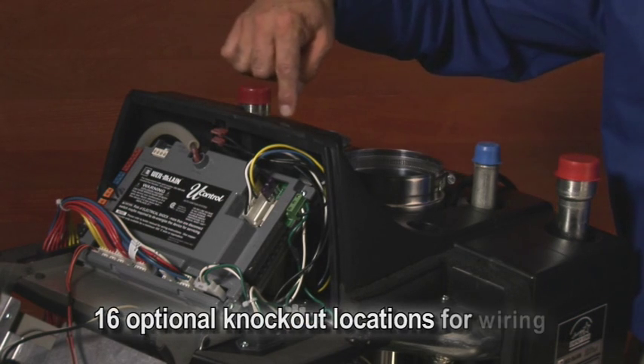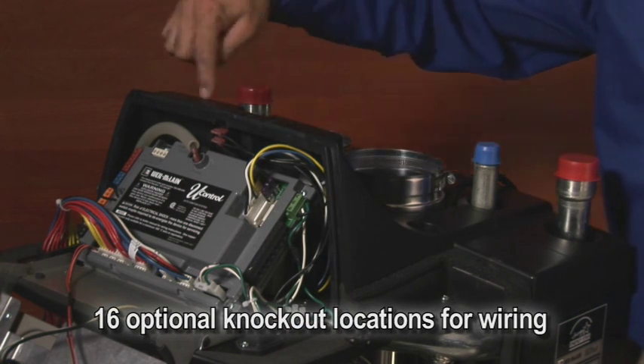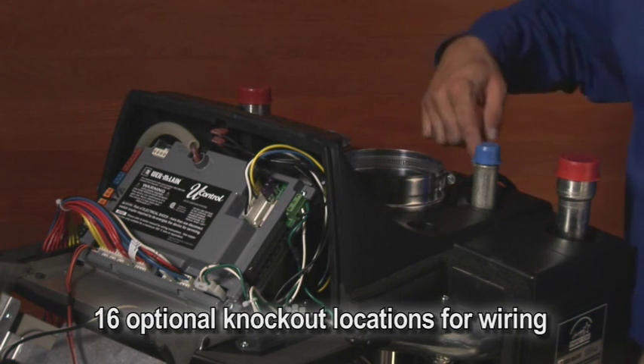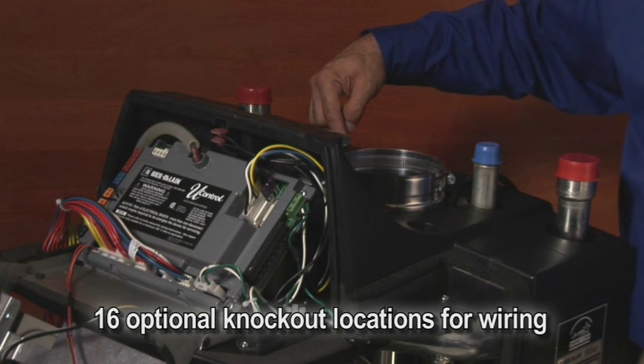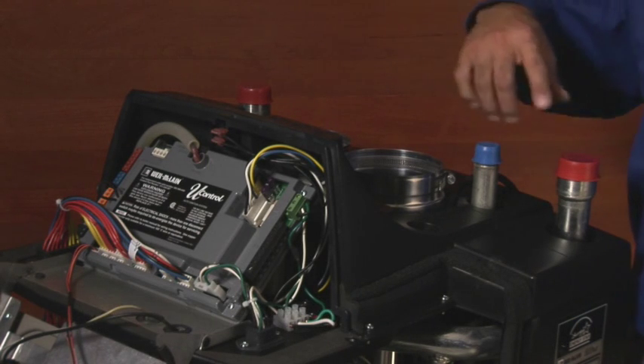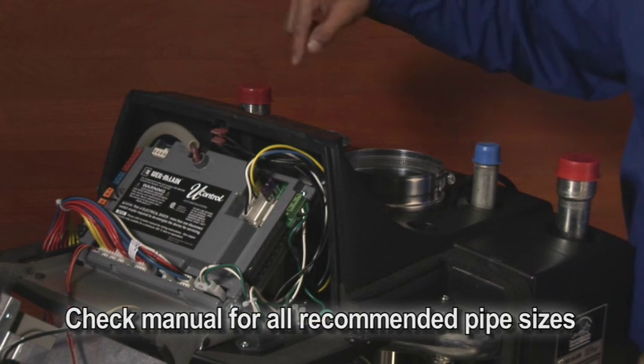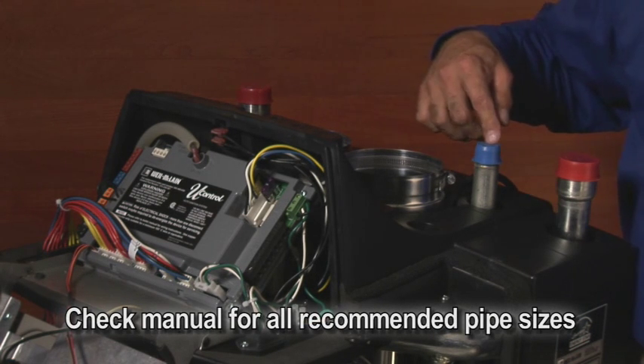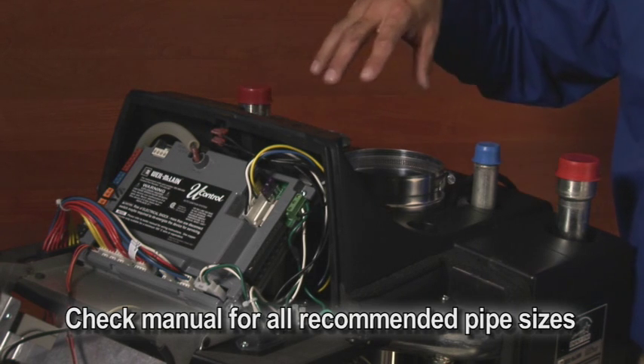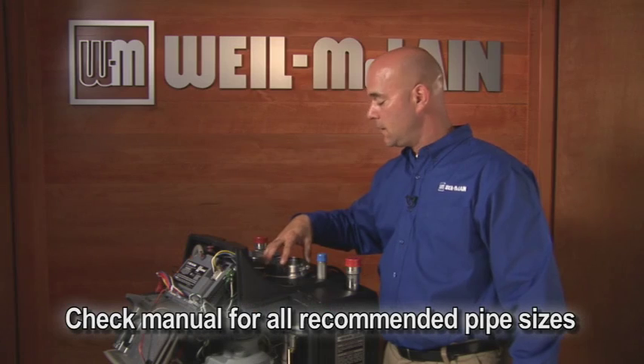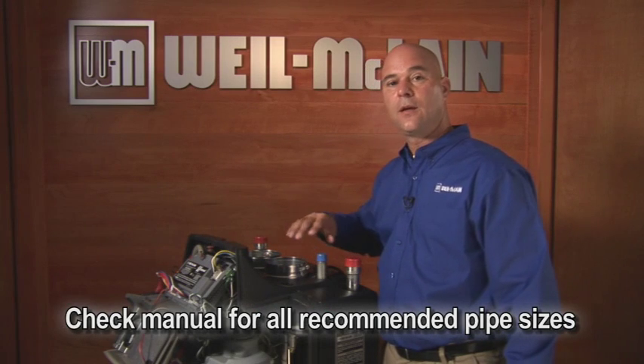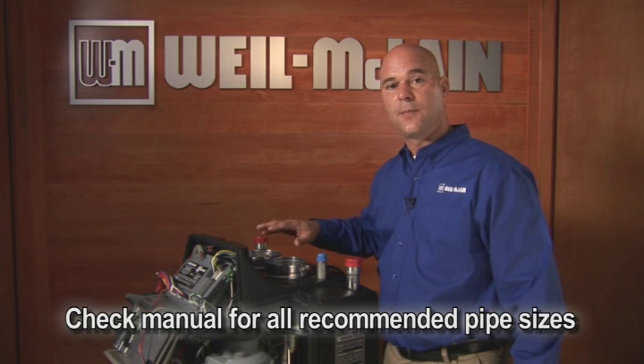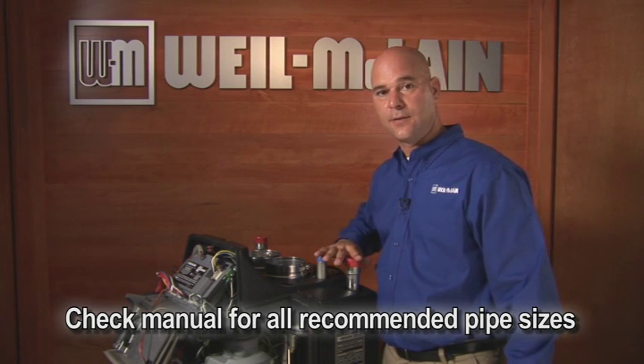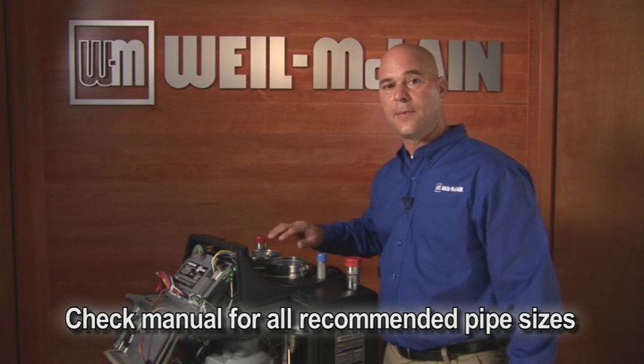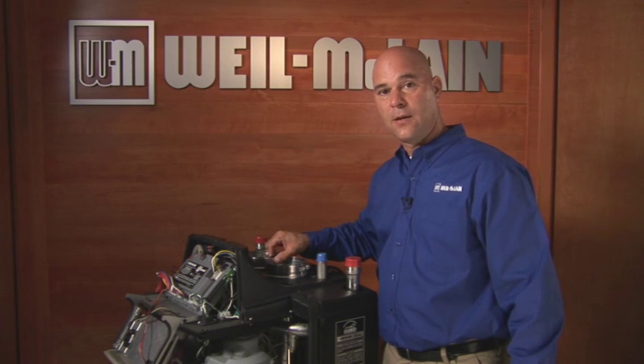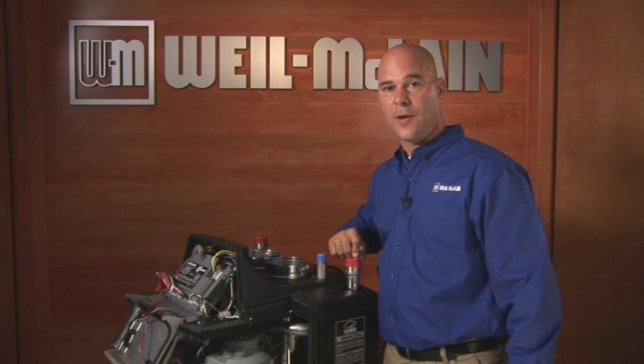There are several locations for electrical connections. There's 6 along the top, 2 down each side, and another 6 along the back of the boiler. In addition to that, on the back of the boiler, we have the supply tapping, the return tapping, and the gas line. We also have the fresh air inlet and the exhaust port. Now, on all of these connections back here, make sure you check the manual. Some of these can be reduced, some of these have to be increased. Depending on the size of the boiler you're installing, you may be able to reduce the vent piping, but you may have to increase the boiler piping.